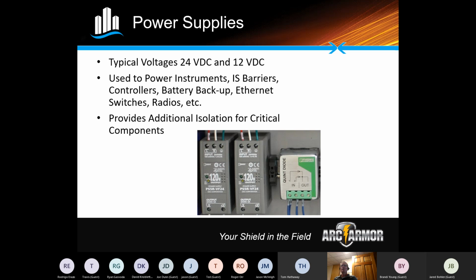So if you have a pressure transmitter out in the field, more than likely you will be sourcing 24 volts power from a control panel to that instrument. They're also there to provide power for barriers, Ethernet switches, your PLC controllers, radios, a number of items that can be located within a control panel. The power supplies can also be married with what they call backup power. So you can put a battery in there and tie the two together to provide 24 volts or 12 volts DC, depending on how you set the panel up for backup power.